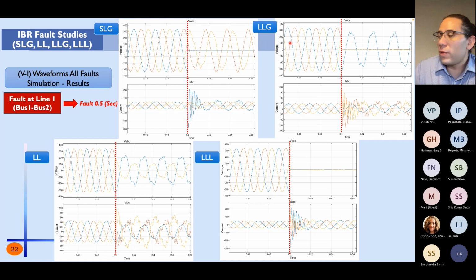On the top right-hand side, I'm showing the line-to-line ground fault. The upper figure represents the voltage and the bottom figure represents the current. On the bottom left, I'm showing the line-to-line fault. Again, all these faults are happening at 0.5 seconds, which I probably didn't mention. And this is happening between bus 1 and bus 2, which is in the previous one-line diagram I showed. It's exactly as it is.